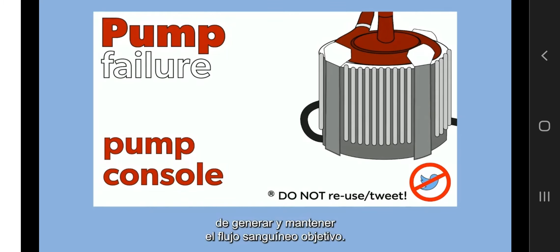Pump failure could be related to the lack of power as the battery becomes exhausted. Connect the ECMO system to power every time it is feasible, check batteries are charging, and before any transport assess the battery's autonomy. Pump failure could also be due to any drive or console malfunctioning not related to power supply.